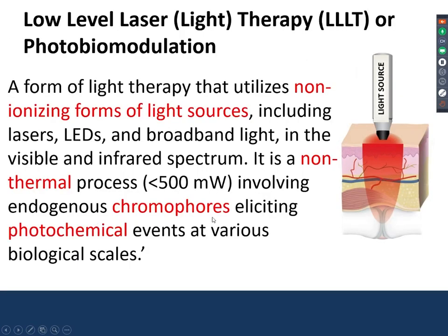So the definition of photobiomodulation is a form of light therapy that uses non-ionizing forms of light, including, but not necessarily, lasers, LEDs, broadband light, and so forth. Generally speaking, the power output of each diode needs to be under 500 milliwatts, otherwise it's a thermal effect. So we want a non-thermal effect, with no heat being produced.